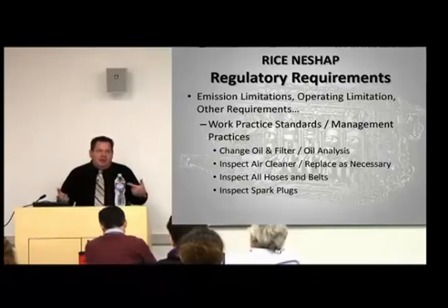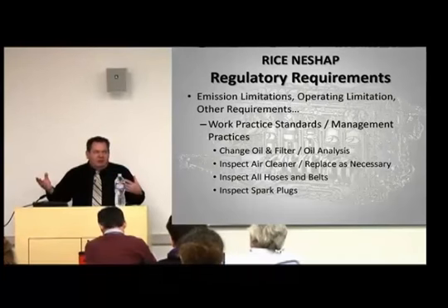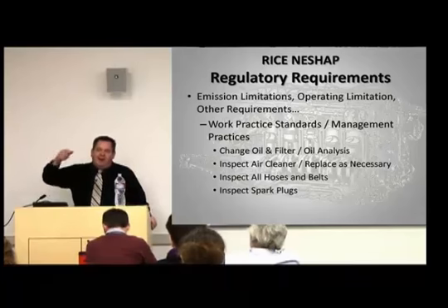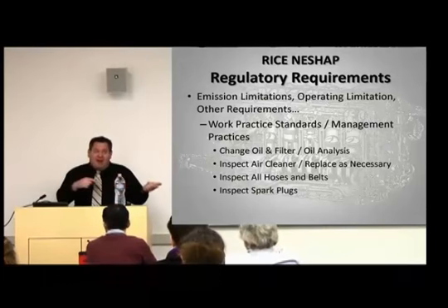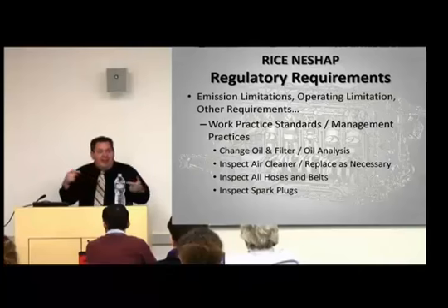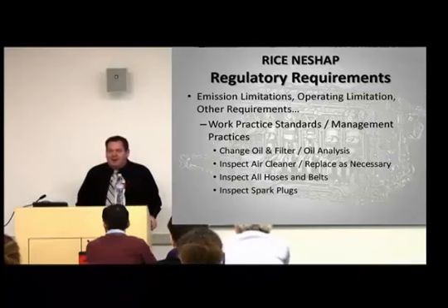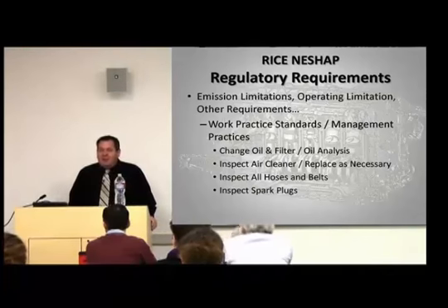So I was inspecting it, and that's what the person giving me the tour was showing me, the little bubble. I'd say, come on, guy, there's like one little wing nut. Take the top of the air cleaner off and look at it. And look at both sides of the air cleaner, because one side will typically be really clean. The other side can be unbelievably dirty. It's amazing how dirty they get. And then in other instances, an air cleaner doesn't even appear to be an air cleaner.